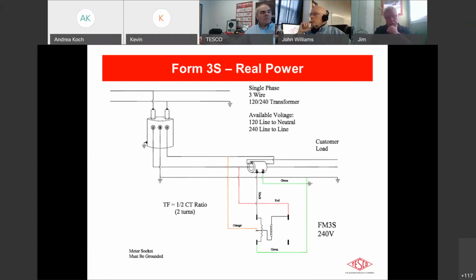Another little thing about this installation is you'll notice that there has to be a 0.5 multiplier associated with the billing on this account. It's because, as you can see, from the X1 on the transformer, the current travels through the CT left to right, and then on the return leg, which goes back to the X2, it comes back in, does a 180 and goes back through the CT in the same direction, and then returns to the transformer. So what's going on here is the CT is seeing the total load of this service twice. So in order for you not to double bill the customer, you have to have a 0.5 billing multiplier on this installation.